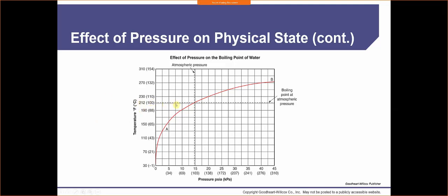If I were to have moisture, just water laying around, that's a lot of heat. That's a lot of BTUs. We talked about BTUs a little bit. If I were to decrease my pressure, I'm able to boil that water at a much lower rate, at 30 degrees. So the heat energy involved of boiling at 212 versus 30 is drastic.